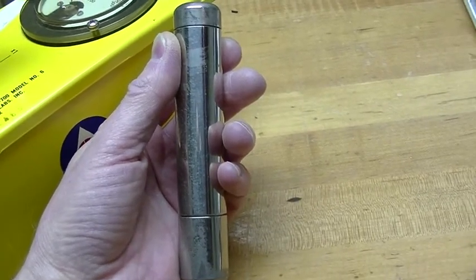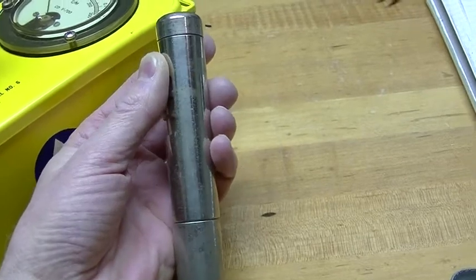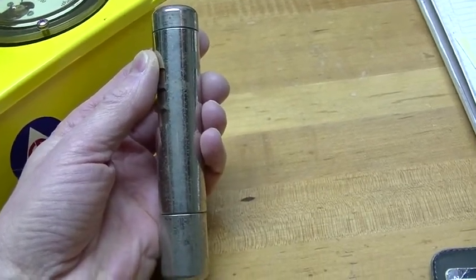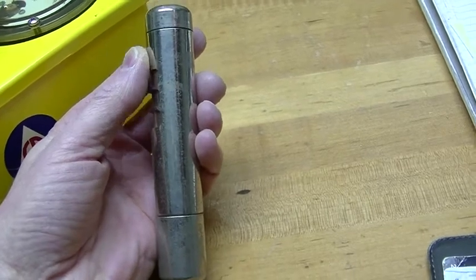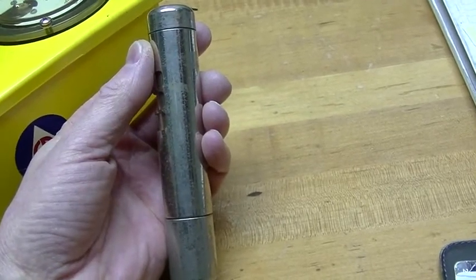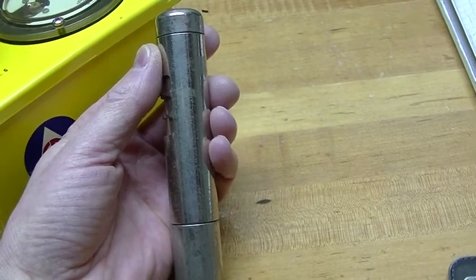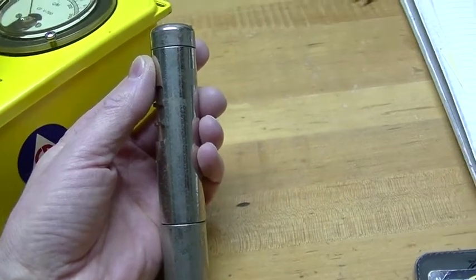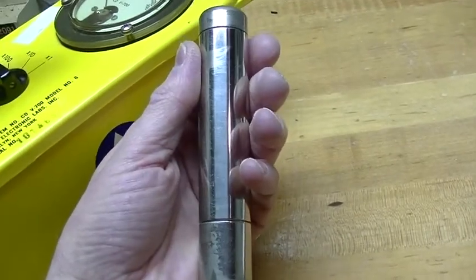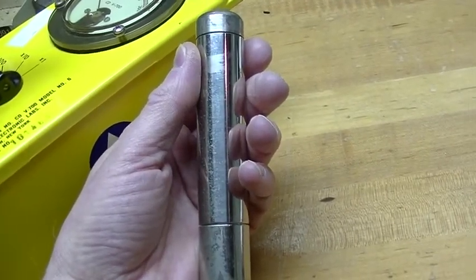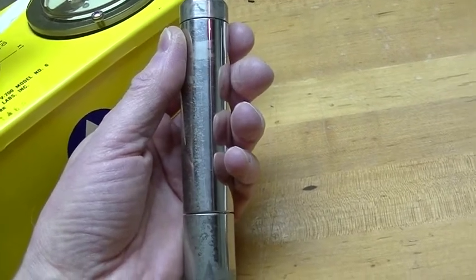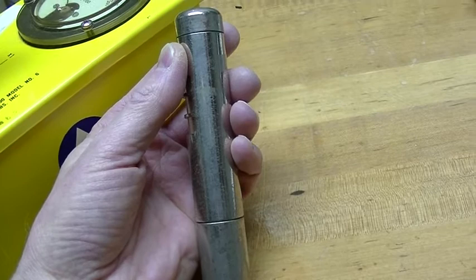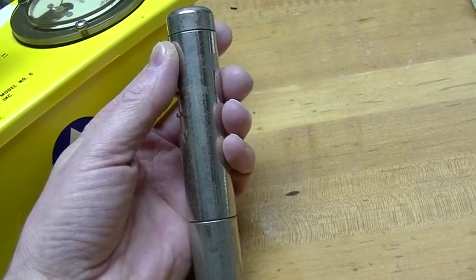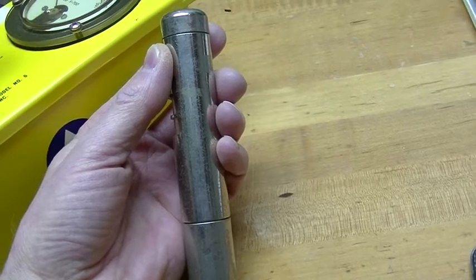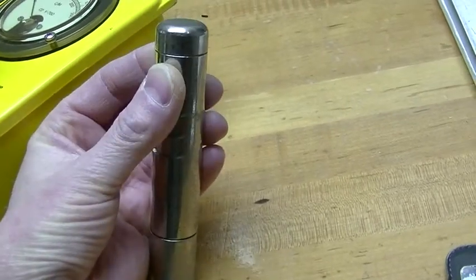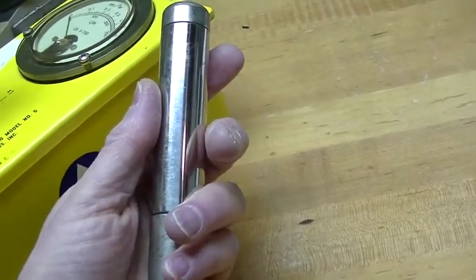And the gas-filled tube is connected up to a high-voltage power supply. Normally, the tube doesn't conduct, but under the right conditions, for example, when a high-energy particle wanders through the tube, the gas is ionized and conducts just for a moment and gives you a click in the headphones, or it gives you a reading on the meter. And the amount of radiation is measured in the number of counts per minute, though there are different methods used now. It's not a complex instrument, but there will be a few challenges when repairing this one.